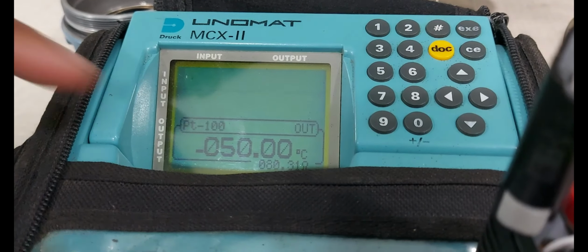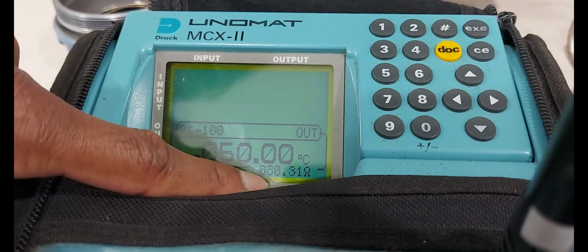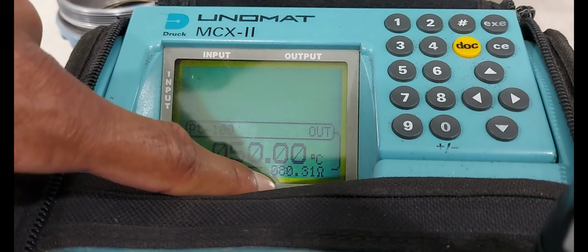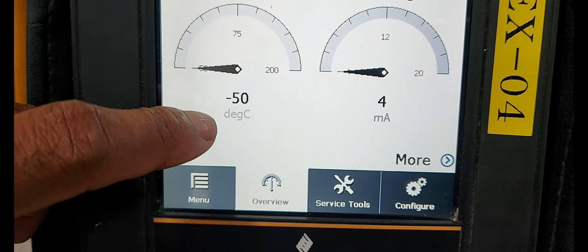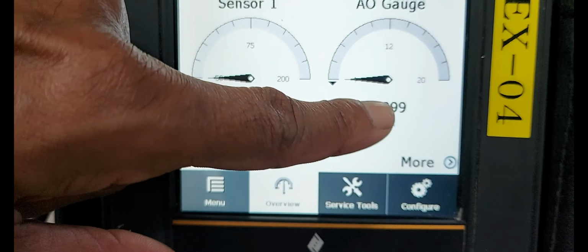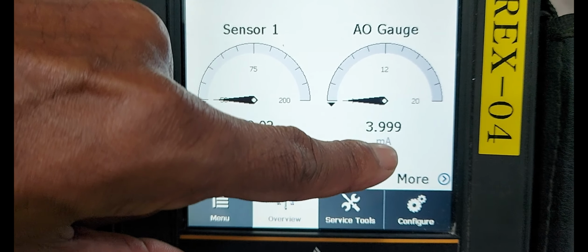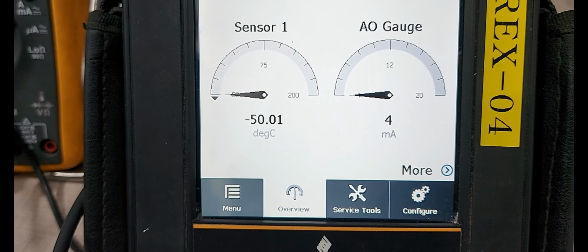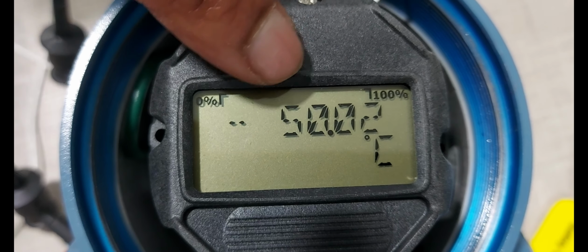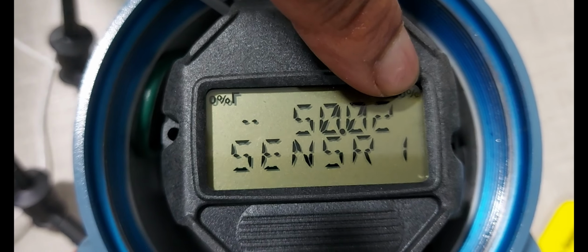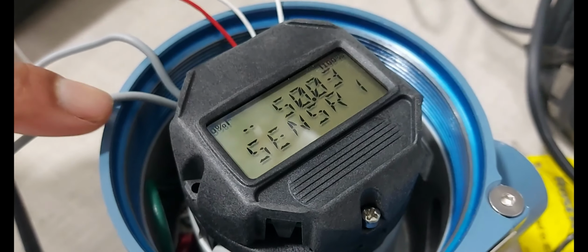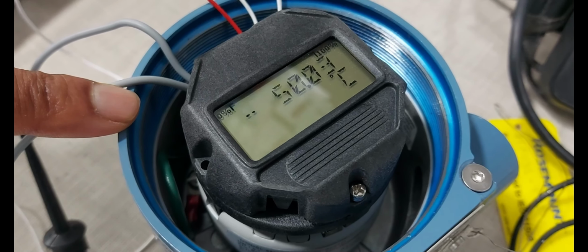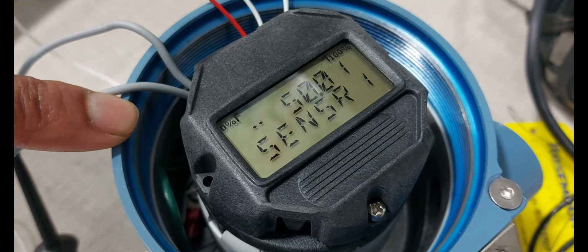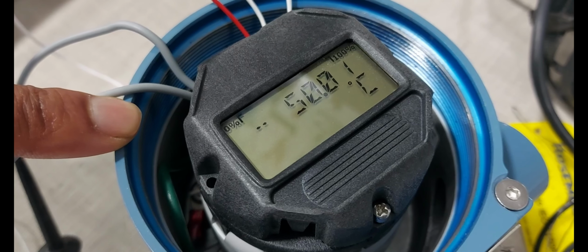The resistance value is 80.31 ohms. Now minus 50 degree reached. Output is showing 3.999 milliamps. Transmitter display showing minus 50.02 degree. Now transmitter calibration is completed. This is only for single sensor calibration.